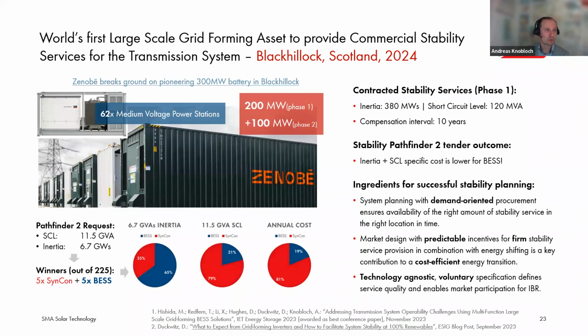And the last example that I would like to give you is regarding the world's first large-scale grid-forming asset that is to provide commercial stability services for the transmission system. It will be built in Black Hillock next year. There was a stability tender in the United Kingdom, the Stability Pathfinder project, the second part of it at least. The grid operator requested a short circuit level of 11.5 gigavolt-amperes and also inertia of 6.7 gigawatt-seconds.